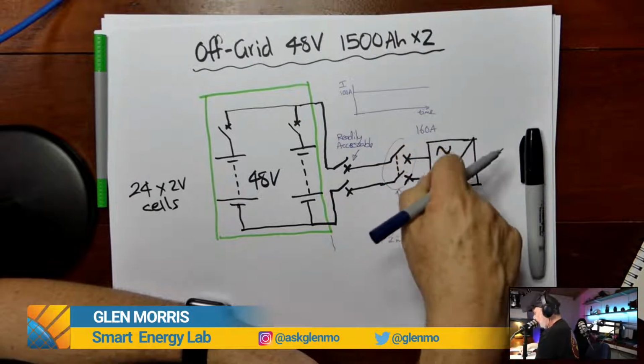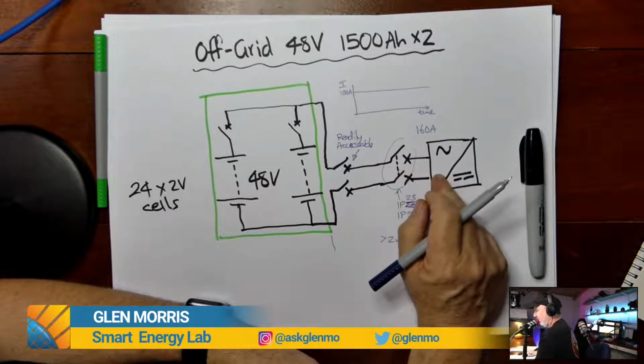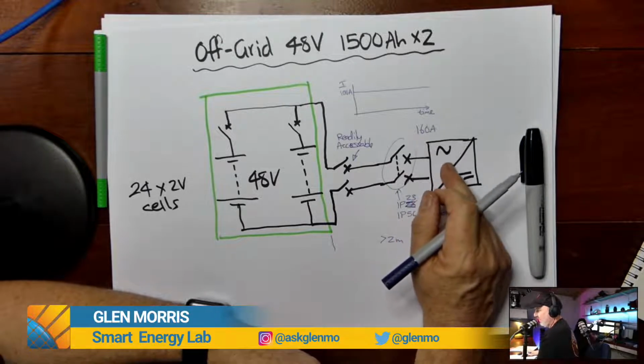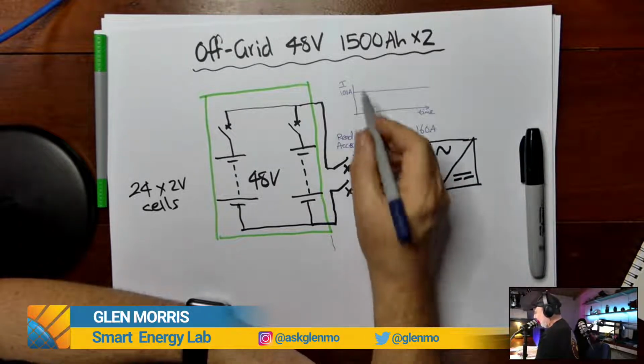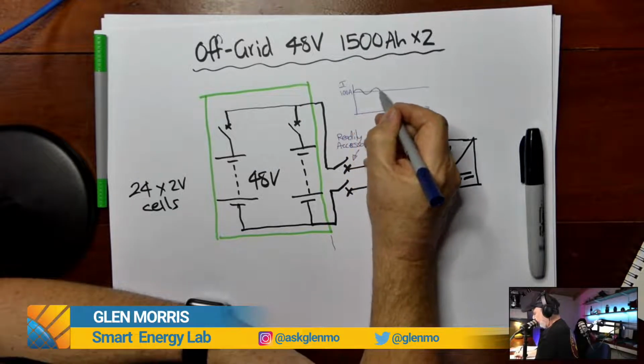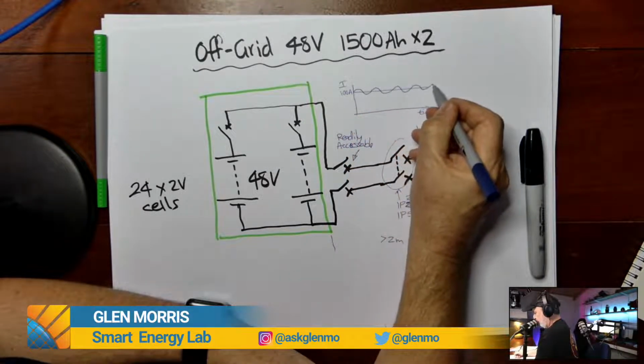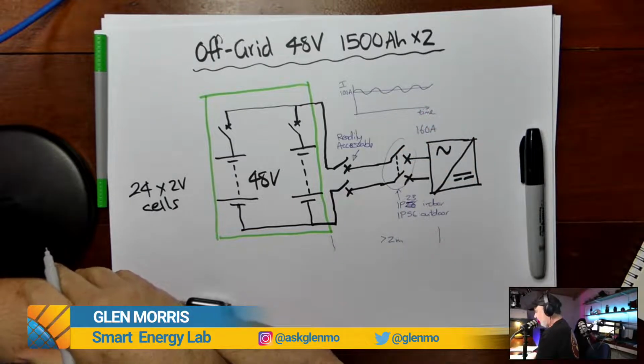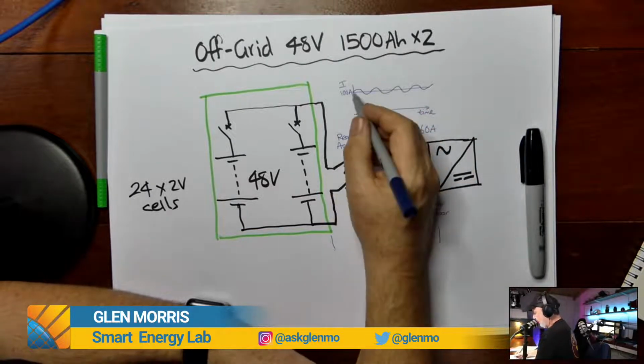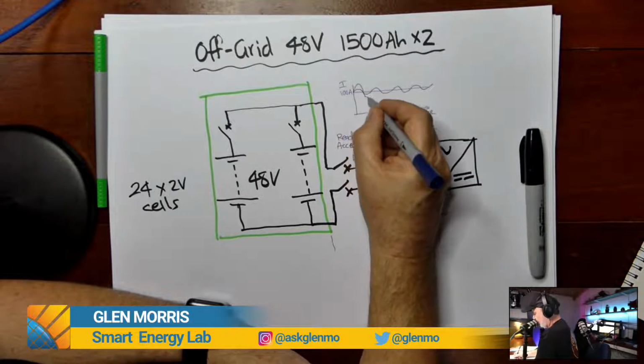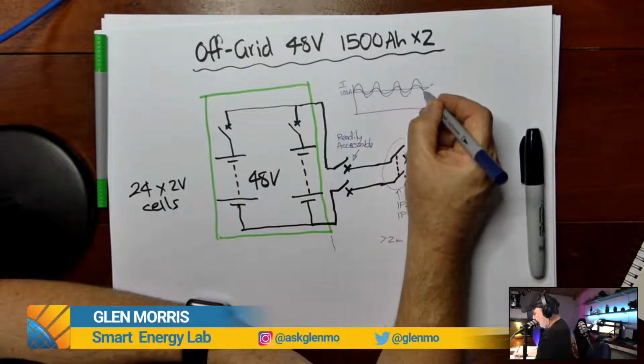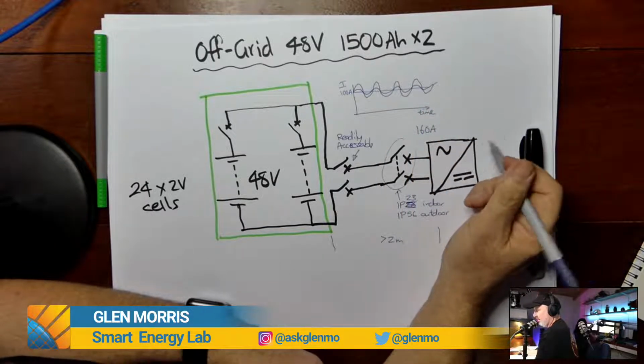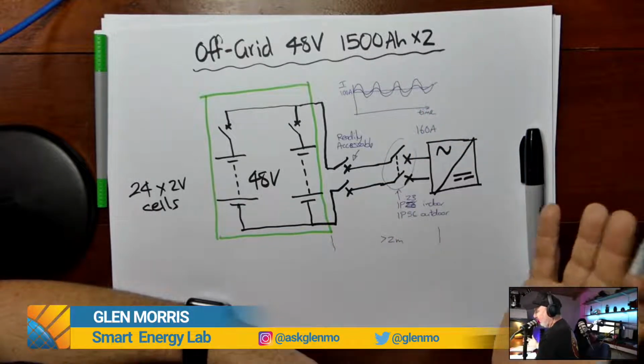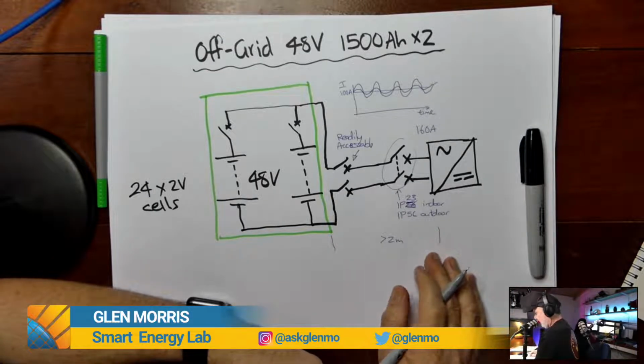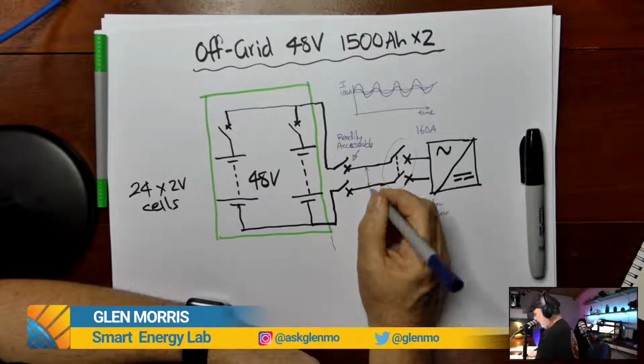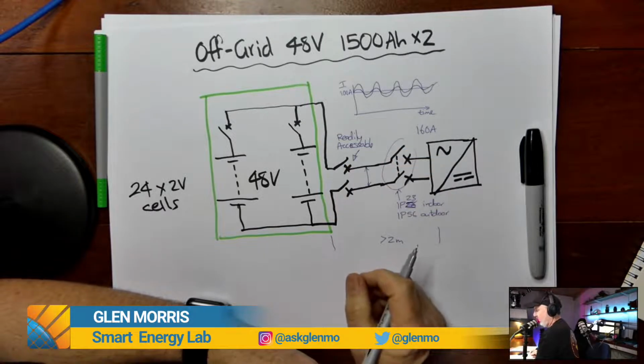But when, particularly, a single phase inverter is creating an AC output from a DC source, it's actually superimposing a ripple on top of that DC base current. So you've got ripple current as well, and the size of the ripple gets magnified by a bunch of factors. Basically the inductance of the DC side of the circuit, which can be just the length of the cables and the size of the cables and the spacing of the cables. So if these two cables here are far apart, you're going to end up with a larger inductor effectively.